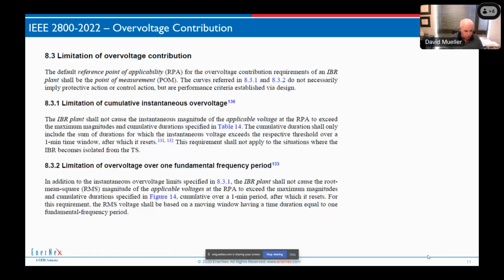Let's talk about overvoltage contribution now. So there's limits of overvoltage contribution. So, this is not as big a deal as in 1547, where a lot of times we're worried about grounding and ground sources and neutral voltage rise and things like that. We don't typically have that with the typical plant. That usually the typical plant has a 3-winding transformer, delta ground, Y ground, delta Y ground, so that the Y ground windings provide a ground source either to the wind plant and or to the transmission system, so that we don't get neutral voltage overrise due to single phase faults and things like that.